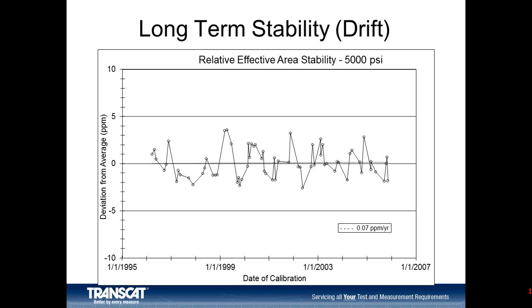Because if you only have a few readings over a relatively short period of time, as you can see at different points along the scale here, like right near the middle, there may be several readings closely spaced in time that appear to have a pretty high trend. But that's just the random nature of things. They happen to align that way. It's not drifting that way and then drifting back the other way. It's just a limitation of the measurement process.